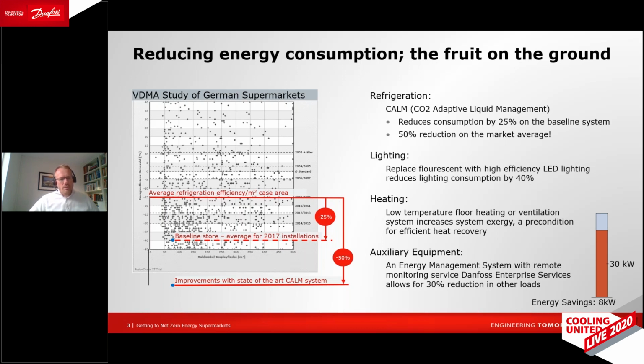And what we've done in this example is to draw from one of our test sites, where we plotted the energy consumption of that store using our new CO2 adaptive liquid management system. Basically what we do here is similar to what Drew was mentioning. We're trying to raise the suction temperature and lower the condensing or gas cooling temperature of the system, and thereby use less energy. What we found was that we could reduce the consumption by 25% on the baseline of 2017, 50% reduction on the market average on the refrigeration side. So quite a reduction, actually.